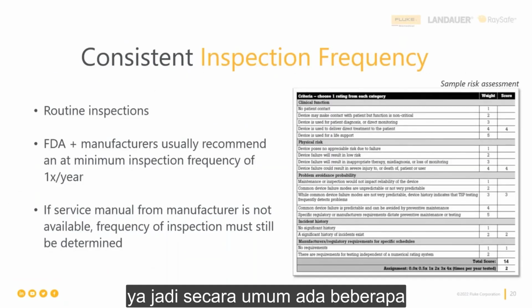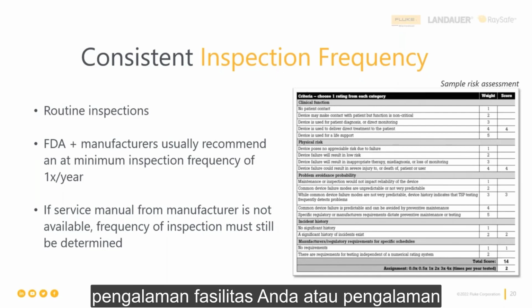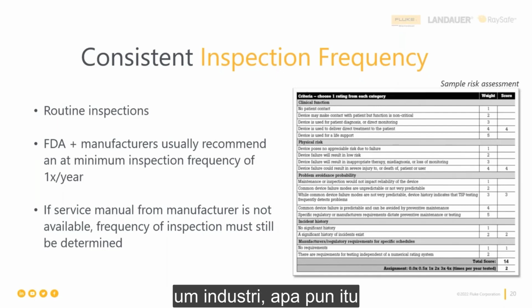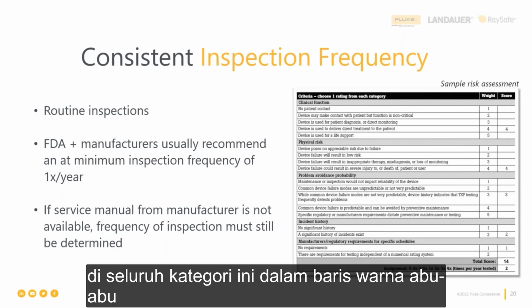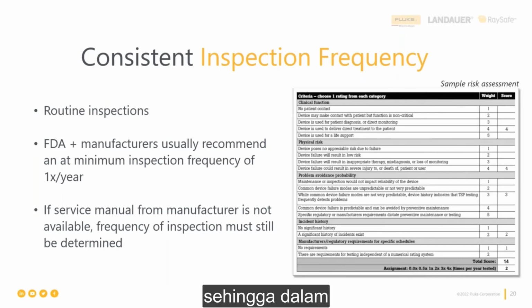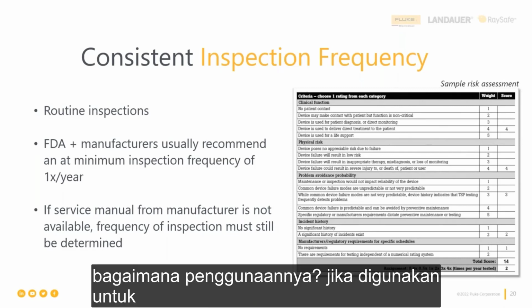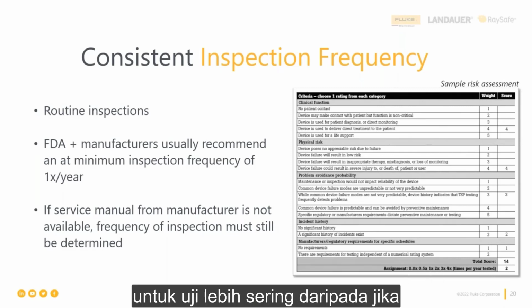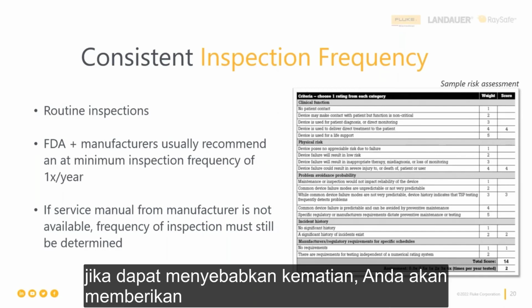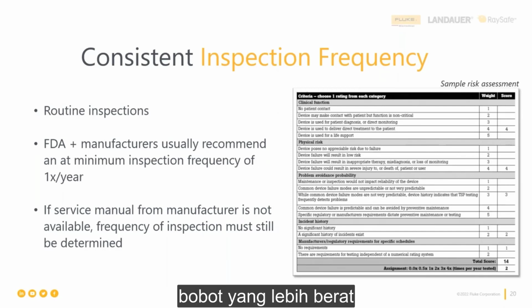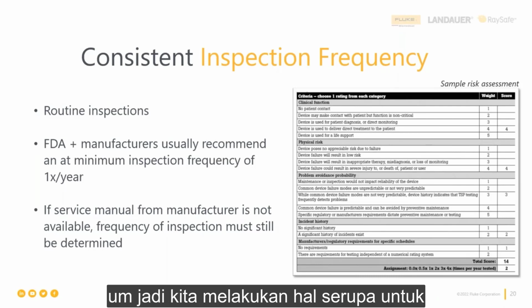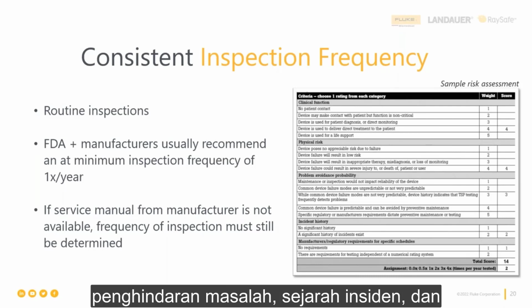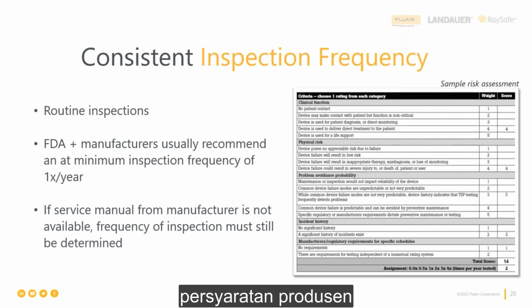So in general, there are a couple of sections on here, but you are going to set a score for either your facility's experience or the industry's experience, whatever it might be, across these categories in the gray bar. So in terms of clinical function, how is it being used? If it's used for life support, you're going to have to test it more frequently than if there's no patient contact. Similarly, for physical risk, if it could cause death, you're going to weight that more heavily versus if there's no risk. We do similar things for problem avoidance, incident history, and the manufacturer's requirements.